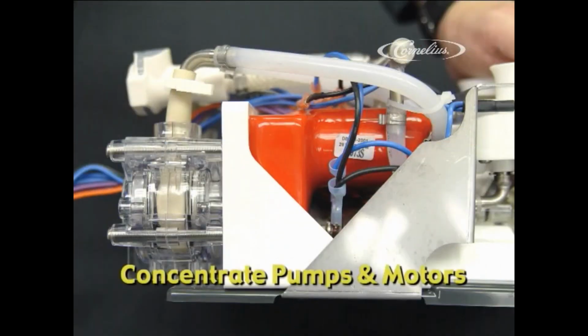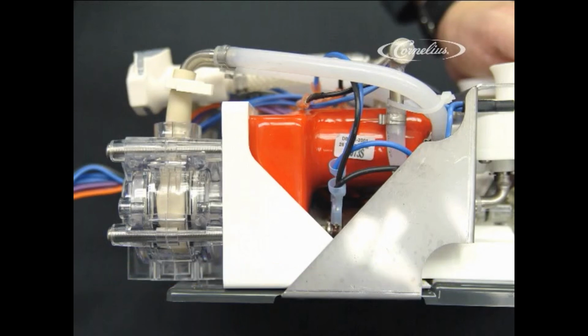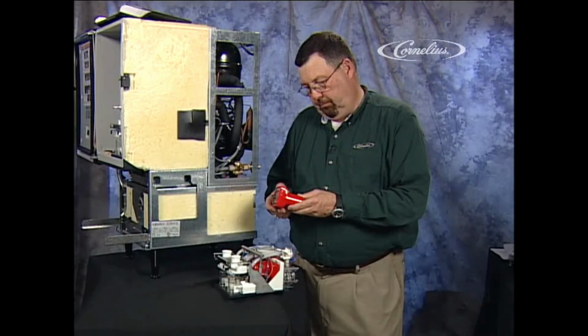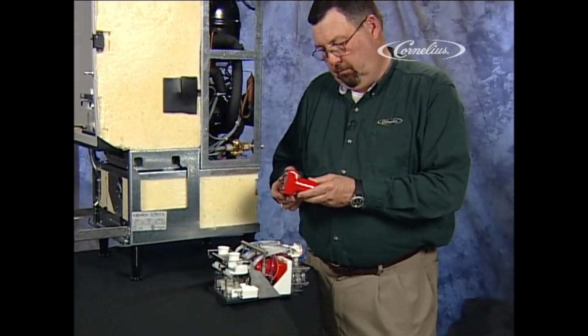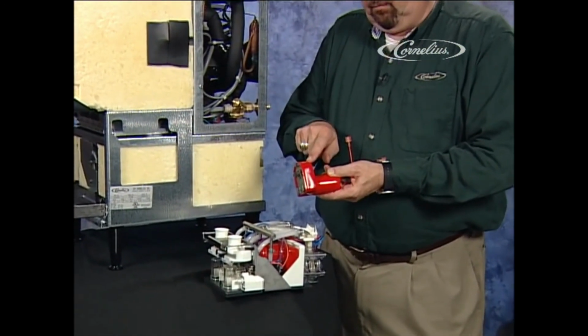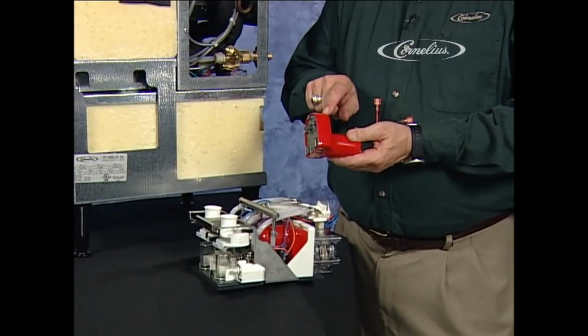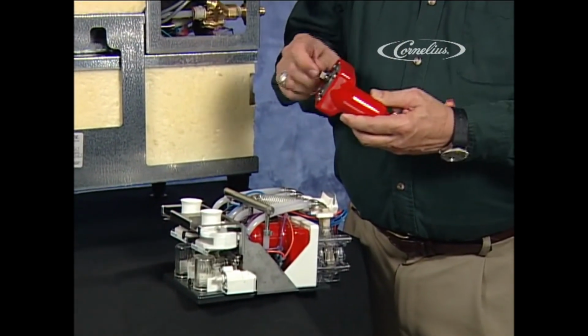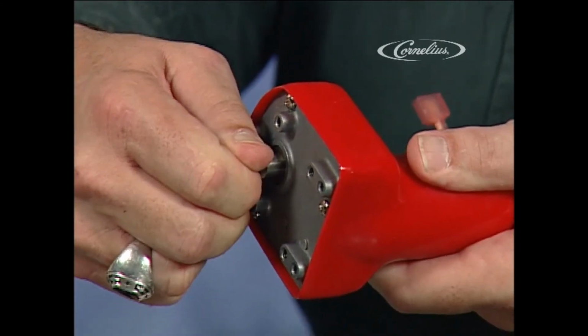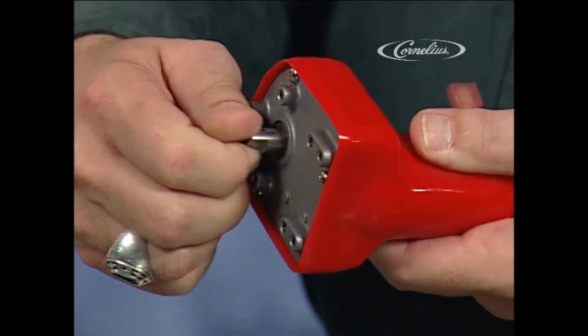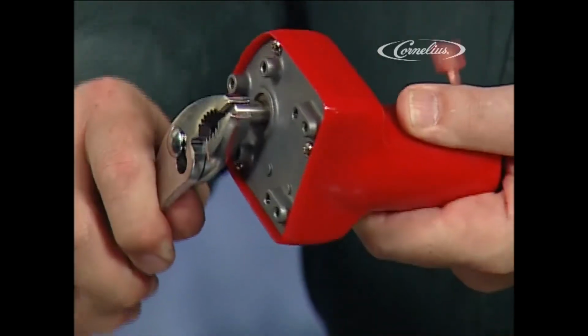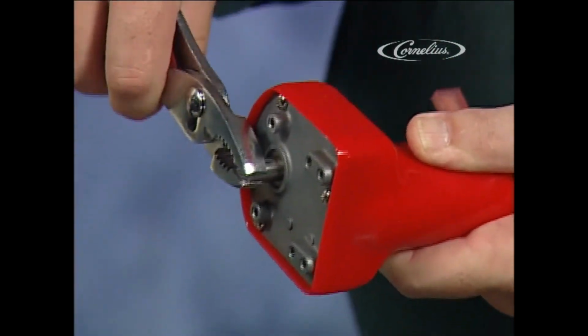These are 28 direct current voltage geared pump motors connected directly to a 3-roller peristaltic pump. Since these are DC motors, they will run backwards if they're not wired correctly. The wires are color-coded for that reason. You will see that the rubber boot that protects the motor from moisture has changed color from orange to red. Although these red motors are identical in application, they are geared differently, so turning them by hand is more difficult. Do not make the assumption on the red motors that if they do not turn, they are locked up. Try with a pair of pliers. If the motor is good, it should turn with pliers.